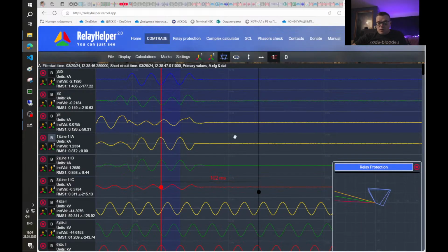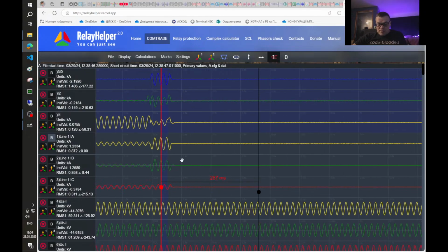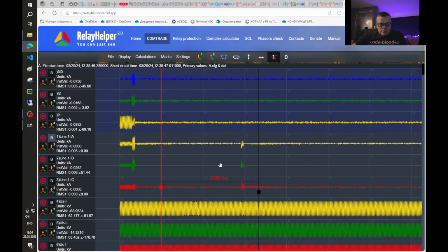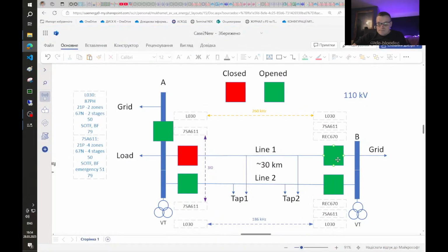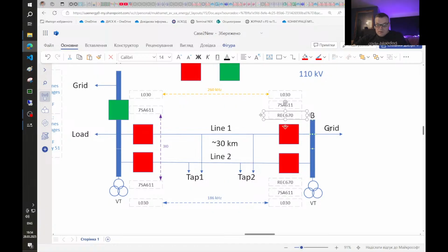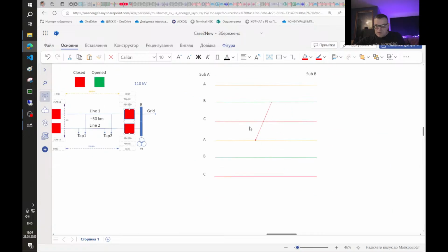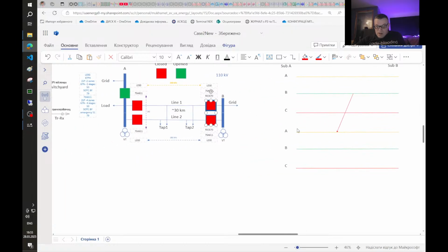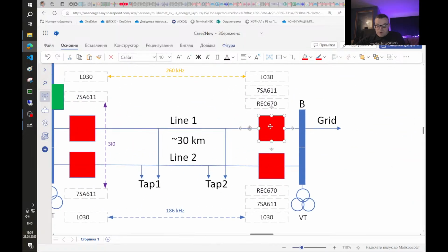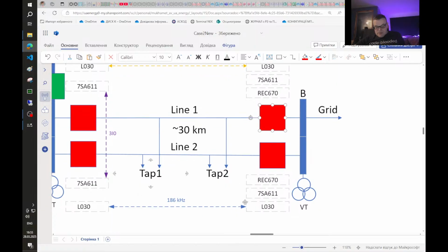So what was the sequence of events? How can I understand? Let's close all circuit breakers. When the fault starts from substation B side, circuit breakers were tripped, so we had this type of fault between phase B of line A, the first line, and phase A on the second line. So from substation B side, circuit breakers were tripped on the second line by phase differential protection, but also by distance protections in Siemens and Hartron devices.